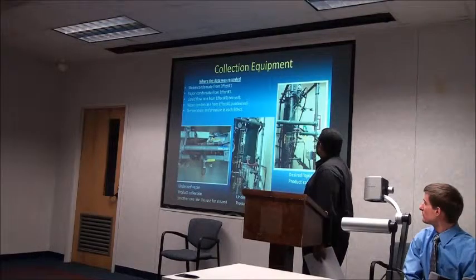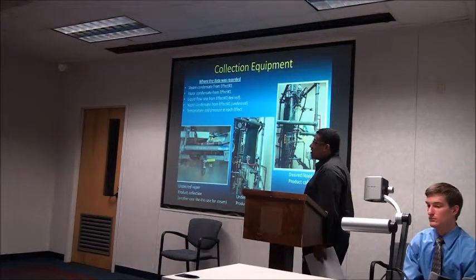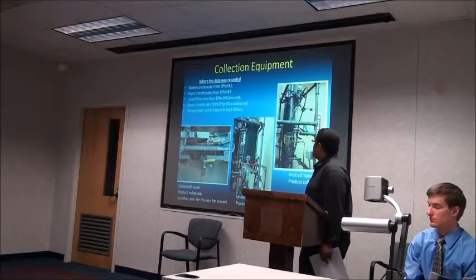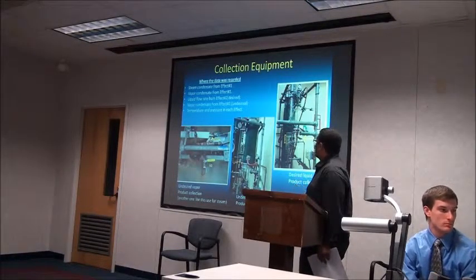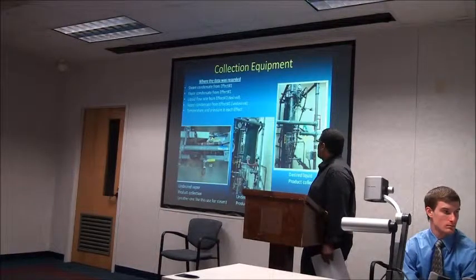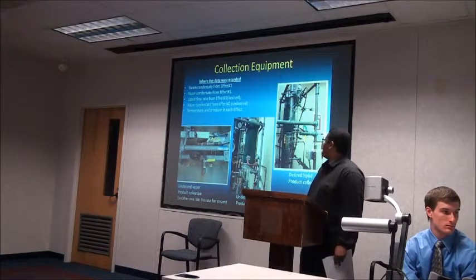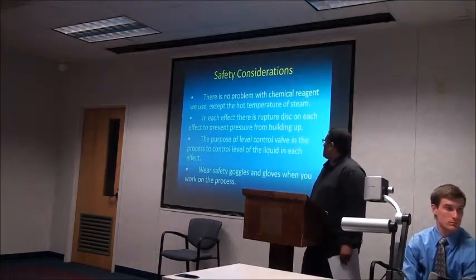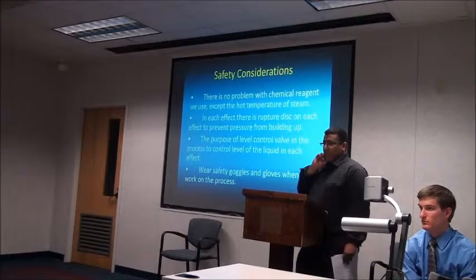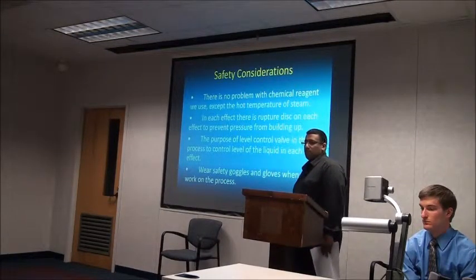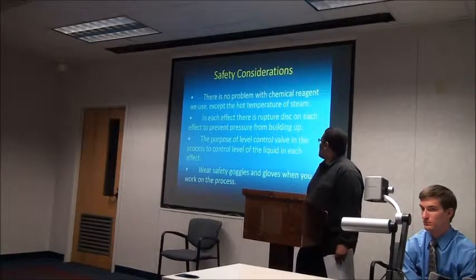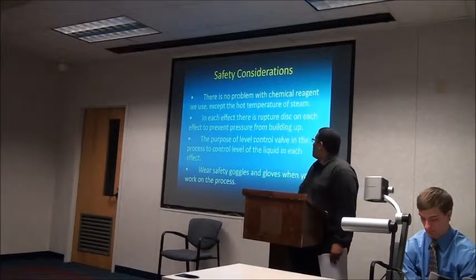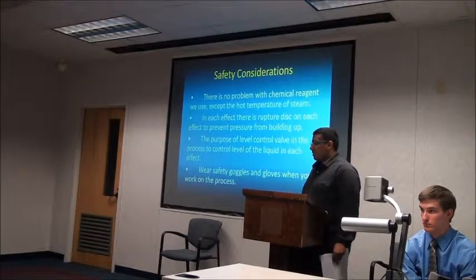The data is taken from this experiment every 15 minutes. We collect the steam condensate from the first effect, the vapor condensate from the first effect, the liquid flow rate from the second effect, and monitor the pressure and temperature in each effect. Safety considerations: there are no issues with chemical reagents, but we must be careful of hot steam. Each effect has a rupture disk to prevent pressure build-up, and there is a level control in each effect.